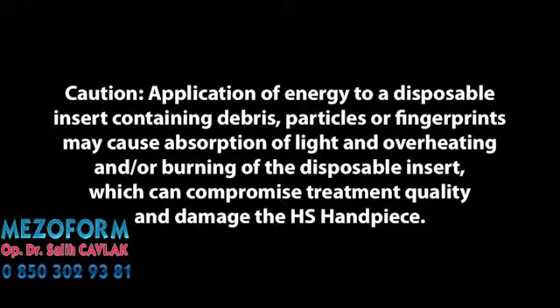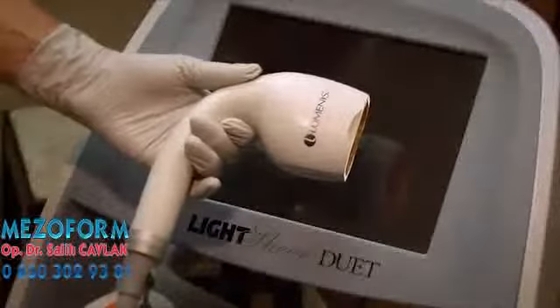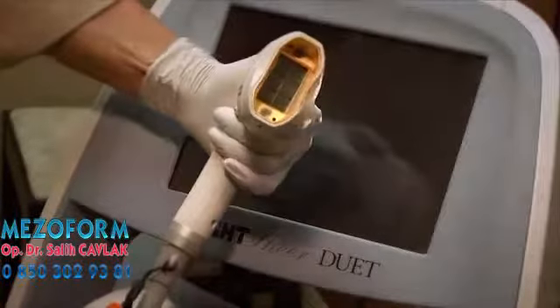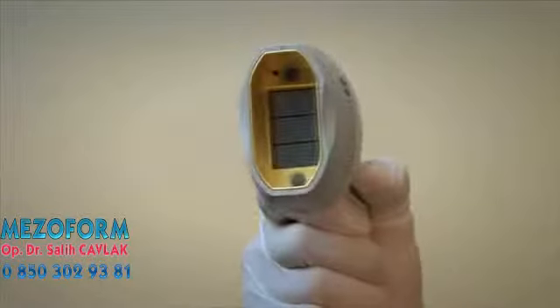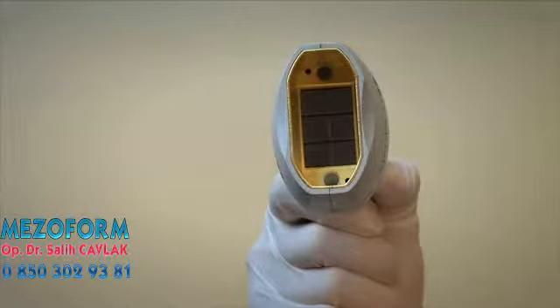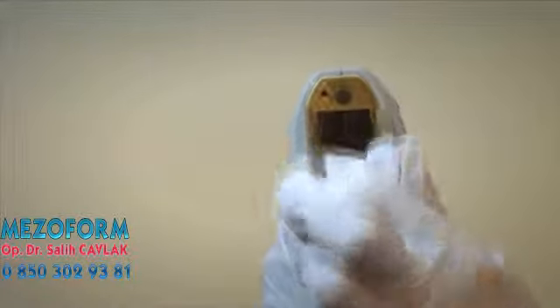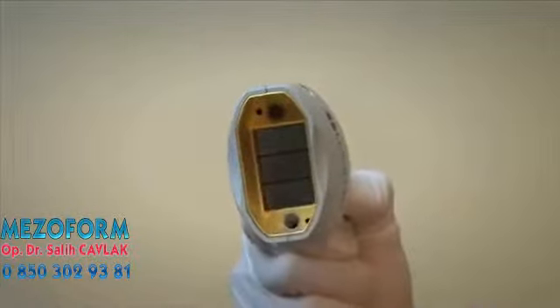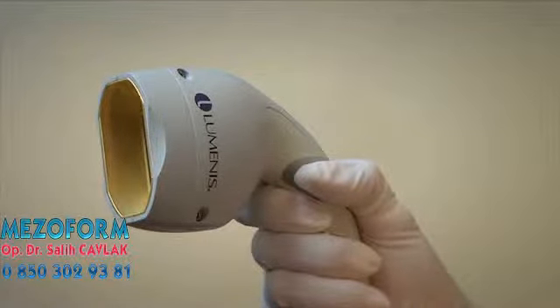Caution: application of energy to a disposable insert containing debris, particles, or fingerprints may cause absorption of light and overheating, and/or burning of the disposable insert, which can compromise treatment quality and damage the high-speed handpiece. While the system is off, inspect the handpiece to ensure that the diode window is clean and free of debris. If the diode window is not clean, use lint-free gauze moistened with alcohol solution to clean the diode window. Then use dry gauze to wipe it clean and remove any fingerprints, stray hairs, or debris. If the diode window cannot be cleaned, do not use the HS handpiece and call customer service for further instructions.